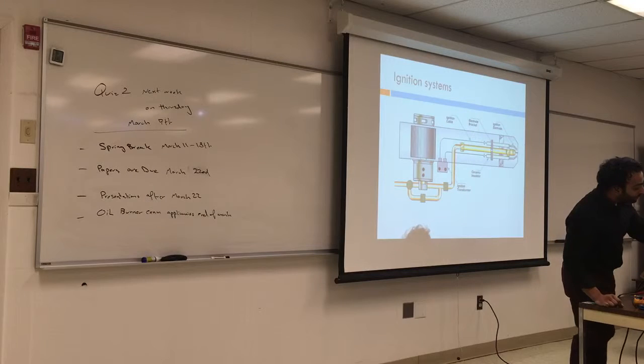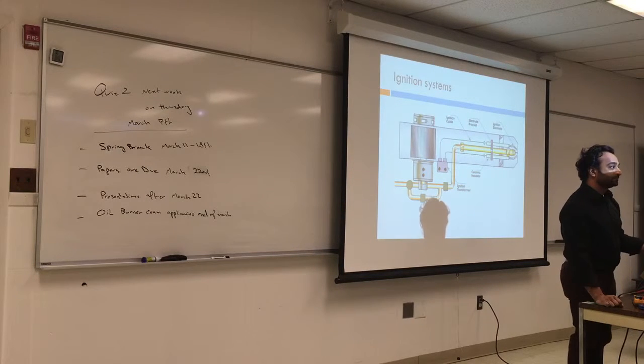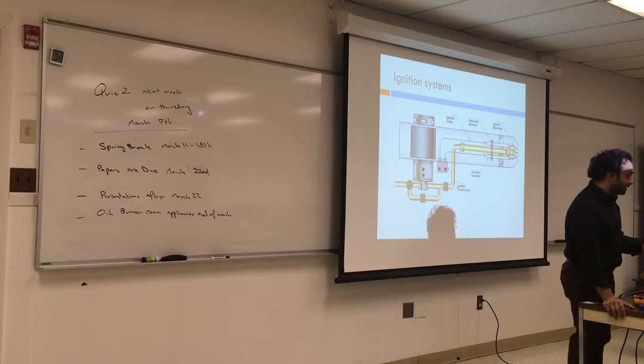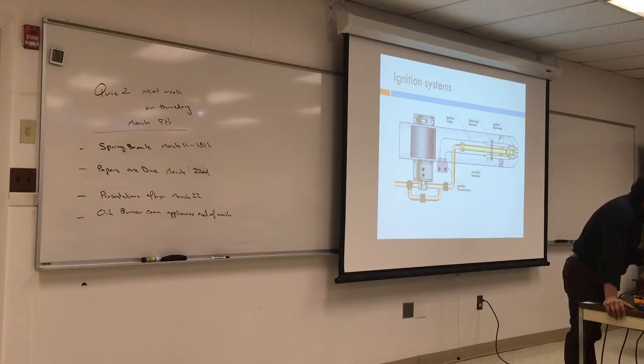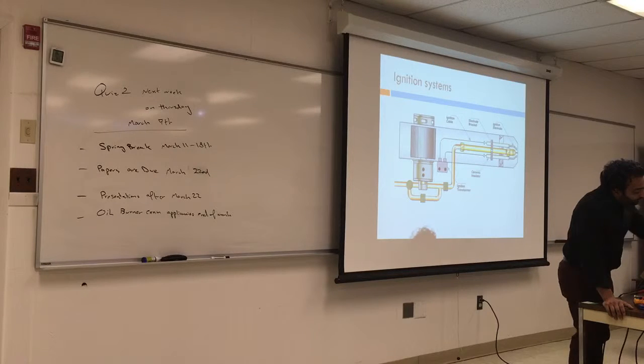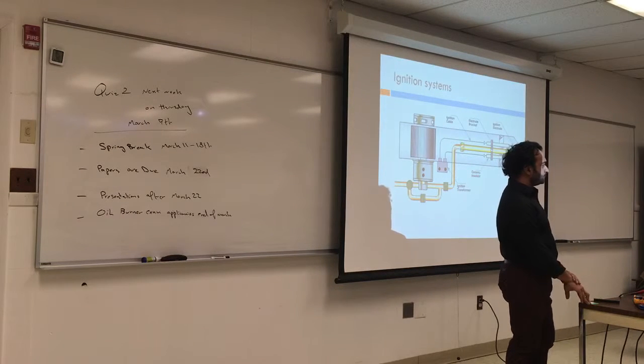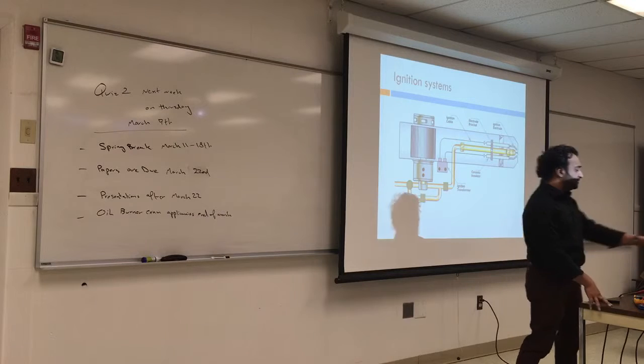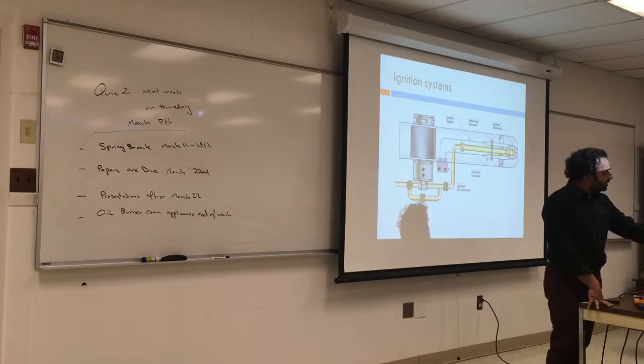Okay, is this a transformer or an igniter? It's an igniter. It's lightweight, it's electronic, so they call them electronic igniters. A transformer is the big one, big, bulky, heavy one. The terminology changes from one field to another, but this is an electronic igniter. And it has the data on it, 120 volts. The output is 14,000 volts, which is a lot. So if you were wiring it and had a transformer, you'd wire it the same way. They're the same size. I mean, the transformer is a little bit bigger, but this is lightweight.